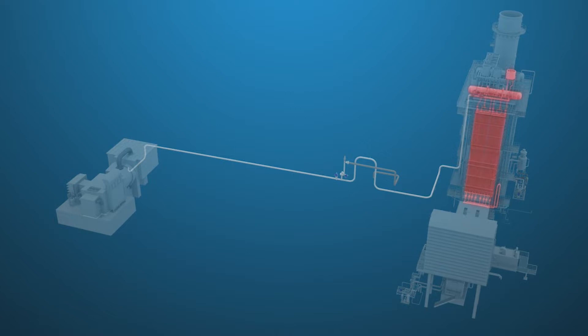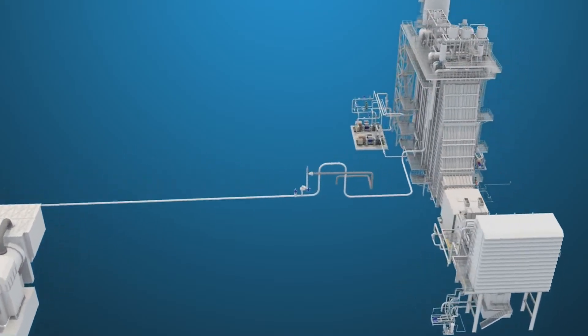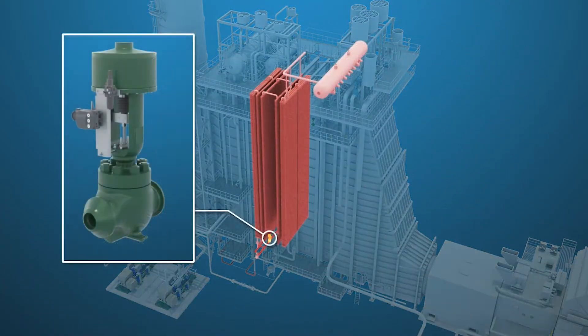Once adequate pressure and temperature are attained, the steam turbine will be placed in service. As the load on the steam turbine is increased, the feed water startup valve will continue to open to maintain level in the HP drum.